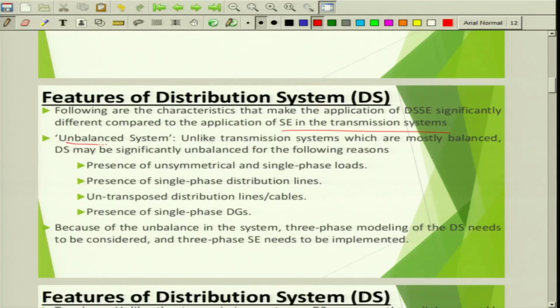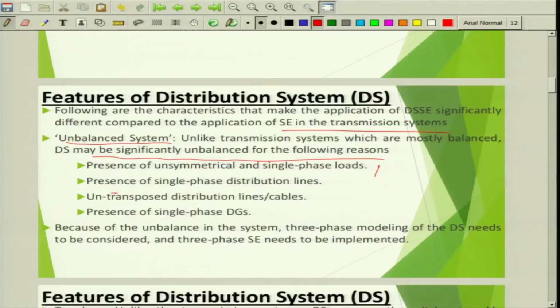state estimator. For example, unbalanced system, which is not seen in the transmission level, because at transmission level systems are mostly balanced. So, distribution system may be significantly unbalanced for the following reasons. One is the presence of unsymmetrical and single phase loads, because most of the home loads are single phase loads, right. So, because of which there could be uneven balance among the load that the distribution transformer is facing, and presence of single phase distribution lines also sometimes, and untransposed distribution lines or cables.